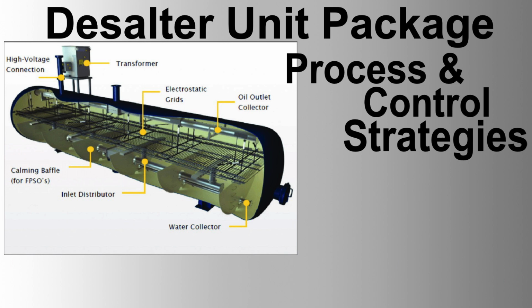Cascade control. Primary controller, LCS401, monitors the separator's oil-water interface level. Secondary controller, FC, adjusts FVSEP101 based on LCS401 signals. Three-phase separator to electrostatic desalter. Feed-forward loop, FTSEP301 flow meter, measures the flow rate of the separated streams. Controller, FFSEP, predicts the composition and adjusts FVDES101 inlet valve accordingly.